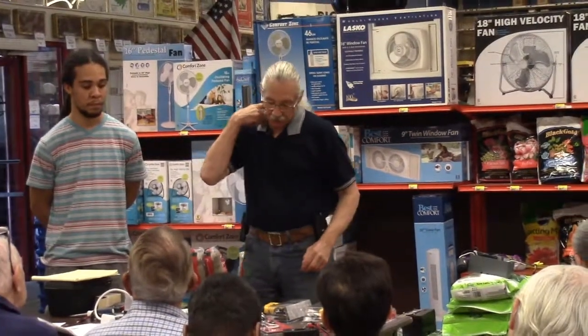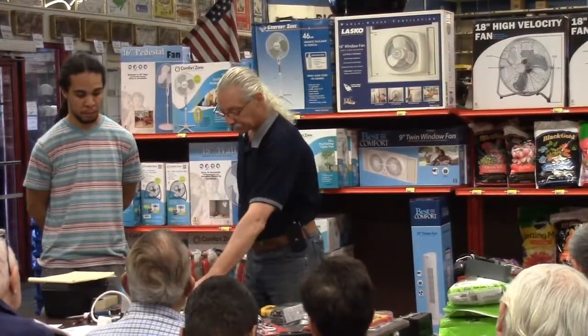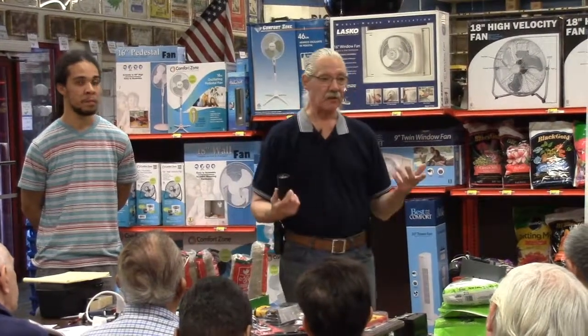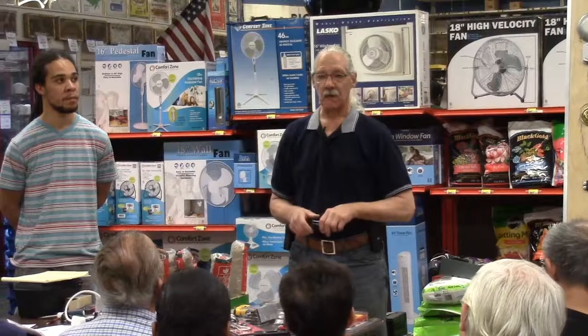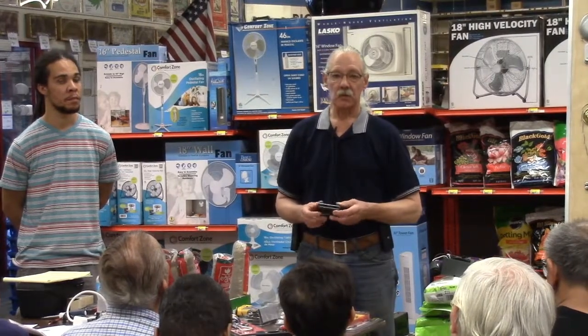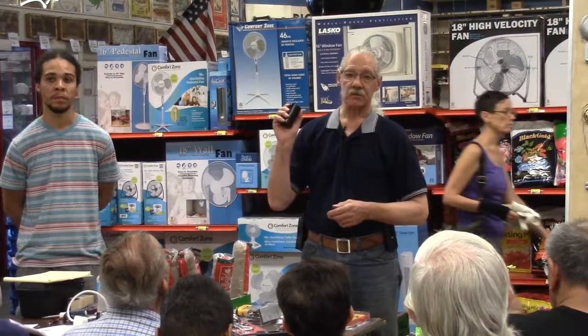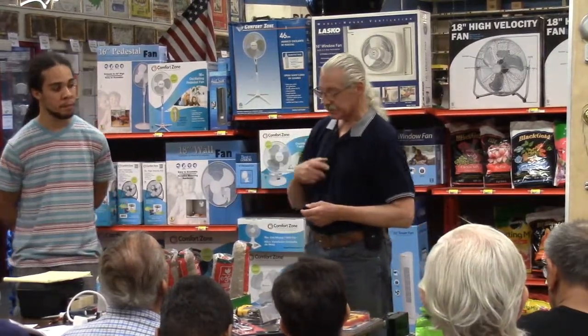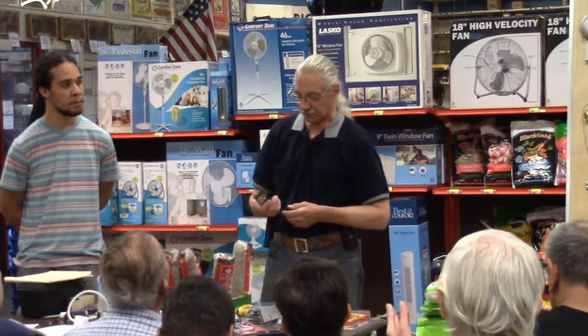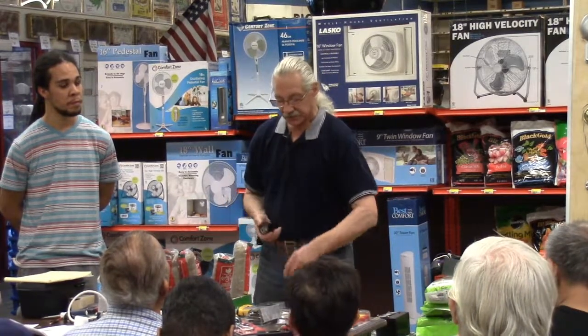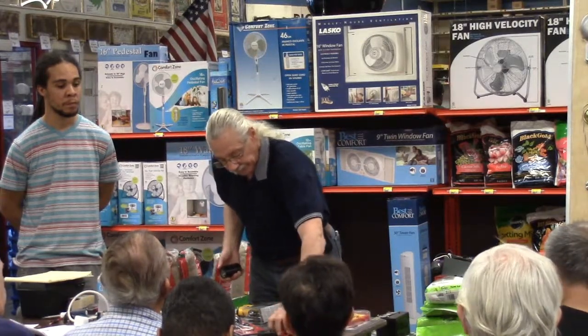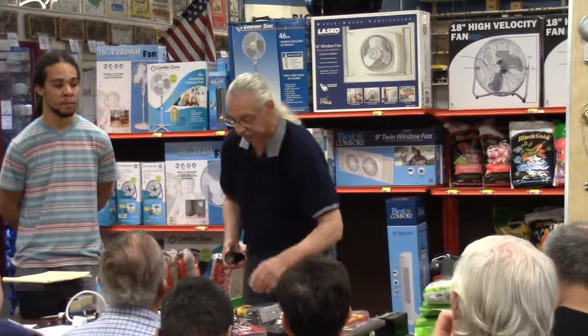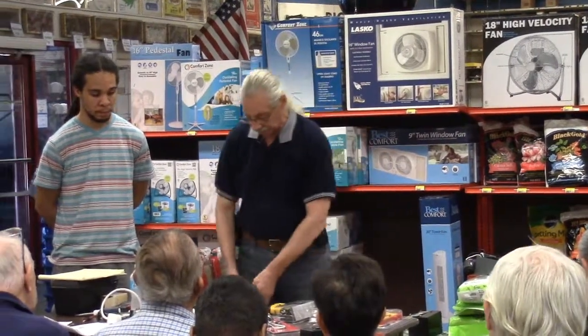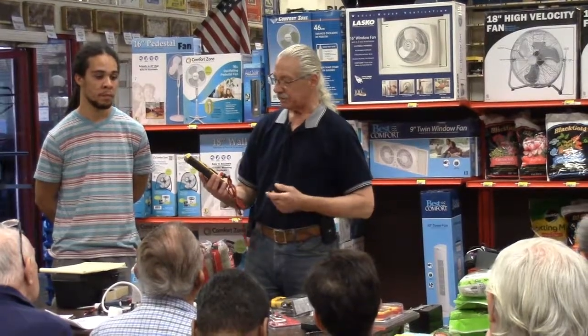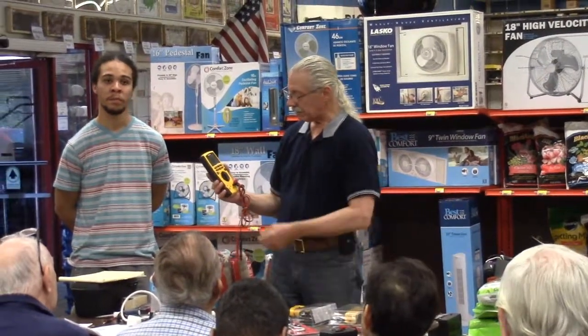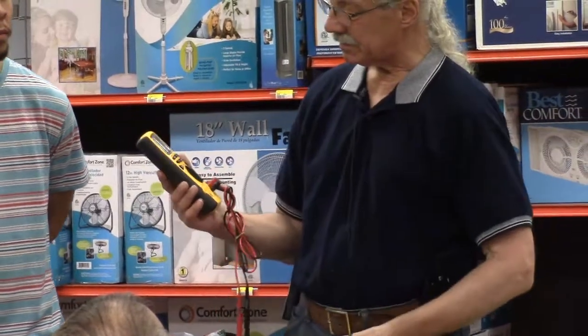One of the things you probably won't go into unless you have some experience with electric already, you're probably not going to want to mess with your furnace and or your air conditioner, is testing capacitors. But we'll go into it just as a side because some people will know what they're doing with electric, quite a bit more sophisticated. And we can't use this meter, we have to switch meters now. We get into the more sophisticated meter, turn it on. I'm already set to capacitance.